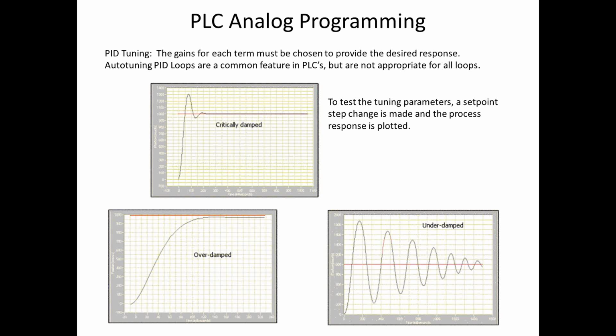In many instances, you don't really need to get to set point that quickly, and it's not critical that it be exact. So a lot of people will over-dampen their control loops. It will take a long time to come up to set point, and it may not actually reach set point at any one time.